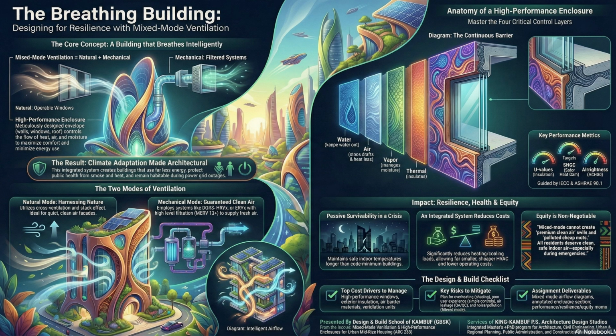And why is that so important for managing cooling? If you use standard glass on a big south or west-facing facade, you are basically installing a giant free heater in the space. It brings in massive amounts of heat, which forces your cooling system to fight that load all day long. Wasting a ton of energy. A ton. So specifying a low SHGC glass, often we're talking below 0.25, is essential to keep the building passively cool and prevent the mechanical system from being massively oversized.